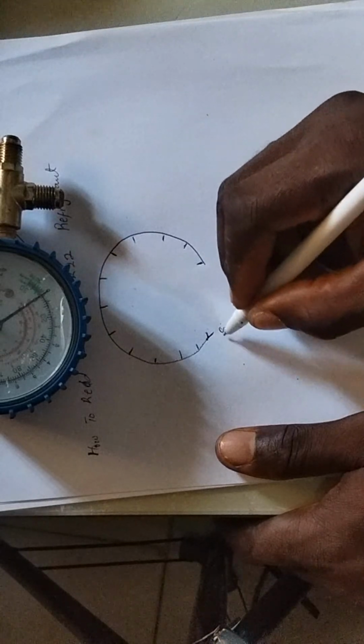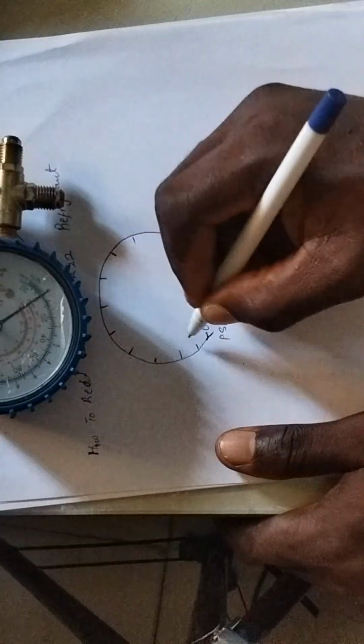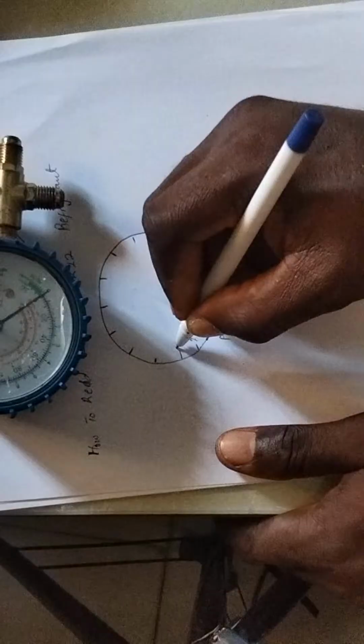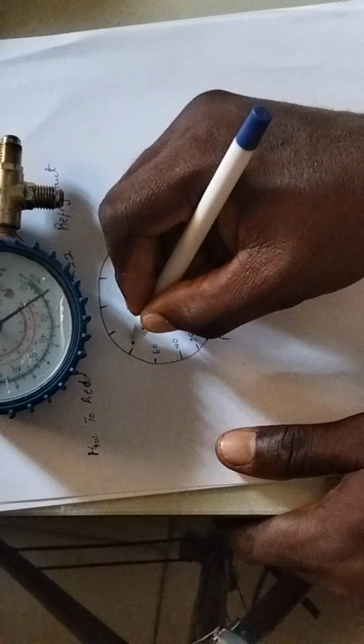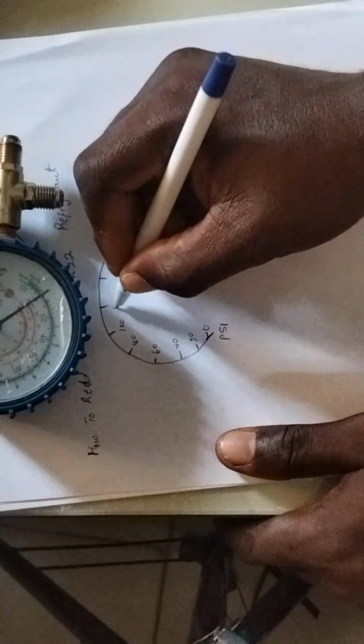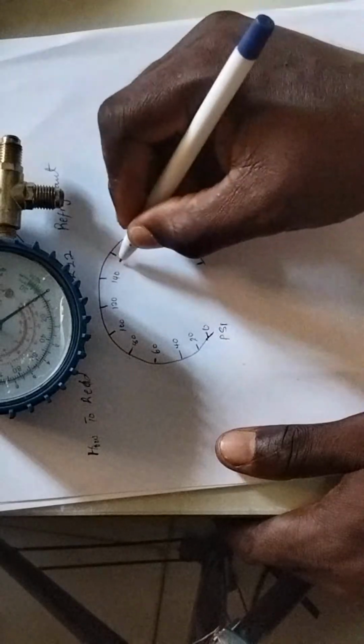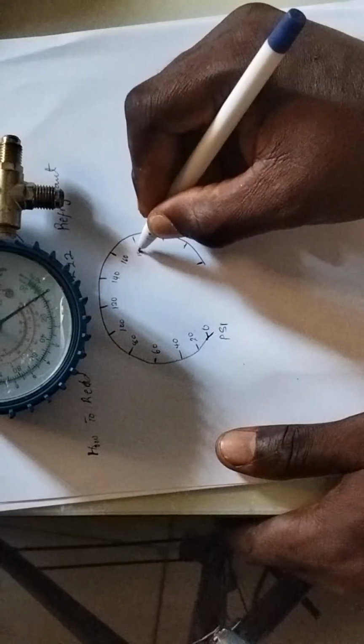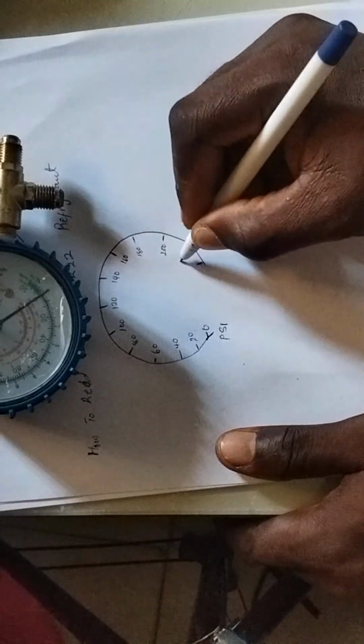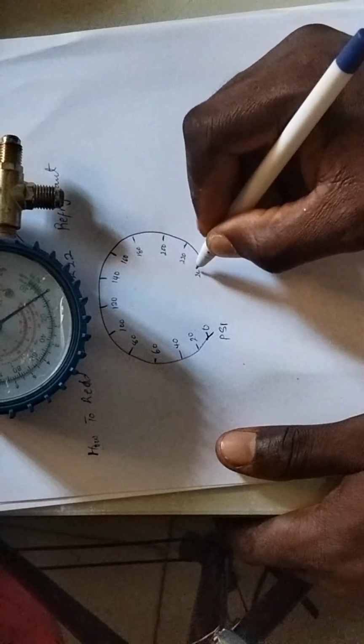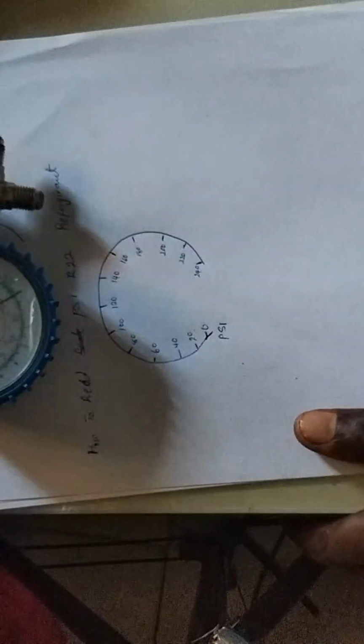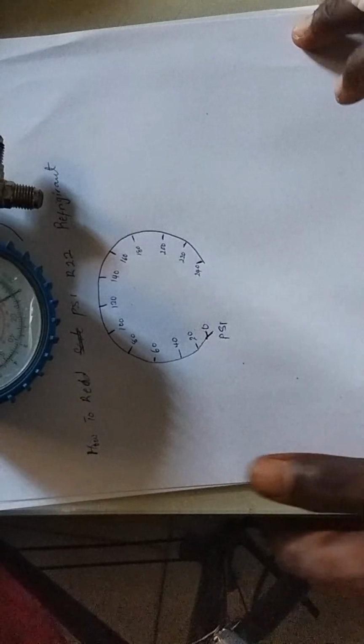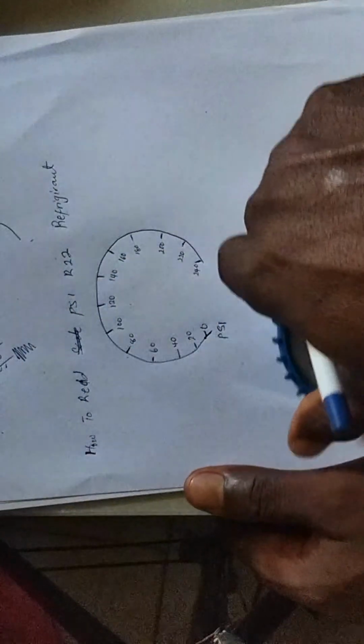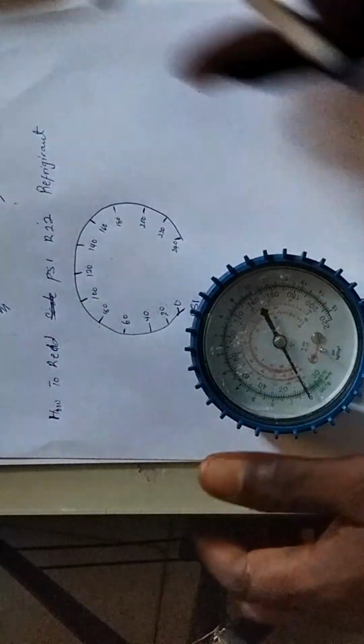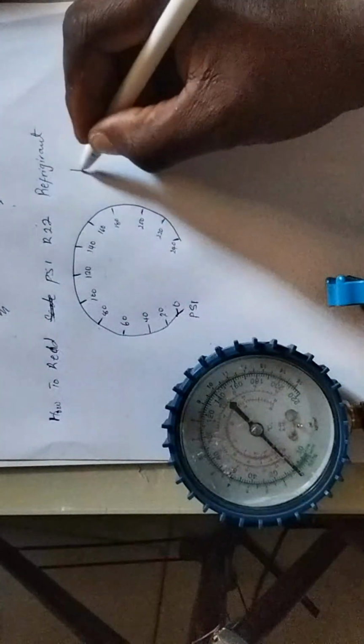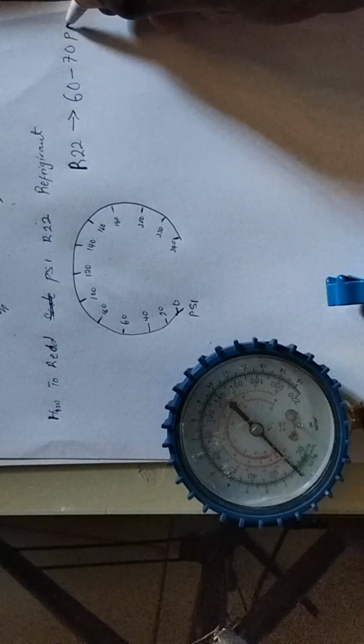So let's say this is psi. This is 0, this is 20, this is 40, this is 60, this is 80, this is 100, this is 120, this is 140, here is 160, here is 180, here is 200, 220, and 240 psi. Now we are dealing with R22 here. R22 is equal to 60 to 70 psi.